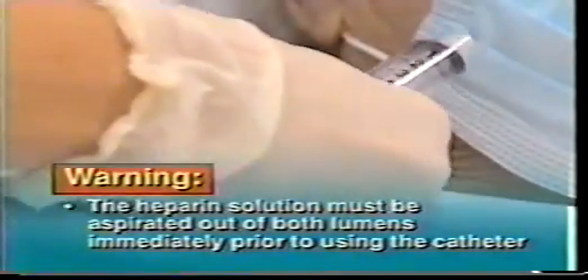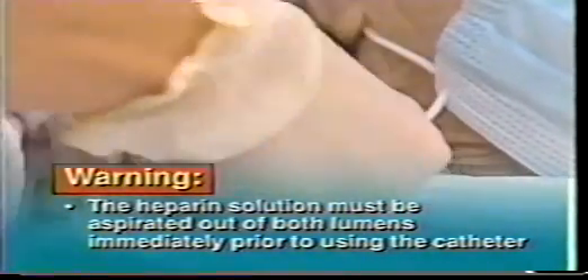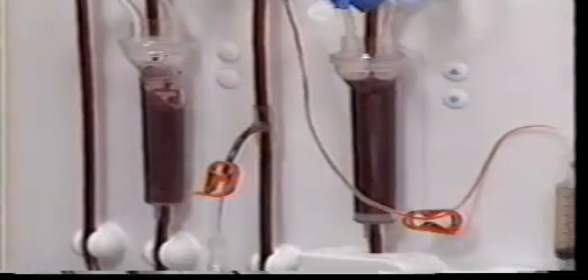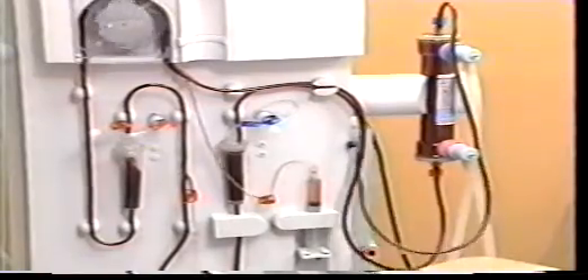In the event of extreme negative arterial limb pressures or repeated alarms for arterial insufficiency, the lines may be reversed in an attempt to improve the blood flow. Warning: to prevent systemic heparinization of the patient, the heparin solution must be aspirated out of both lumens immediately prior to using the catheter. Before dialysis begins, all connections to the extracorporeal circuit should be checked carefully. During all dialysis procedures, frequent visual inspection should be conducted to detect leaks and prevent blood loss or entry of air into the extracorporeal circuit.